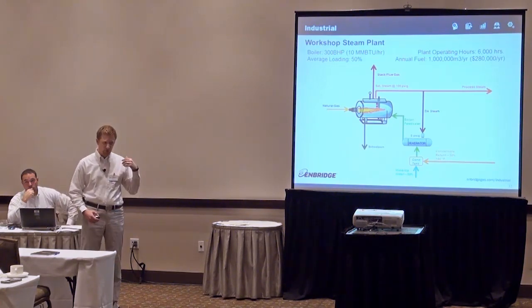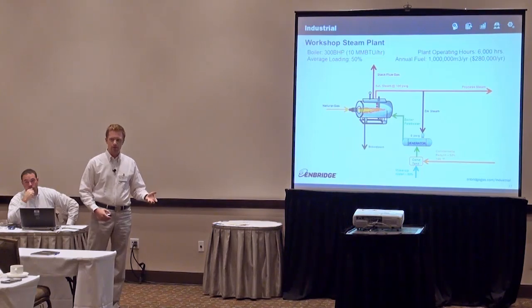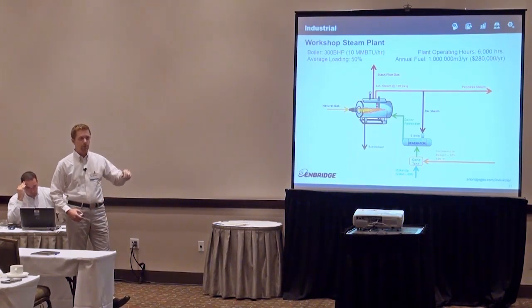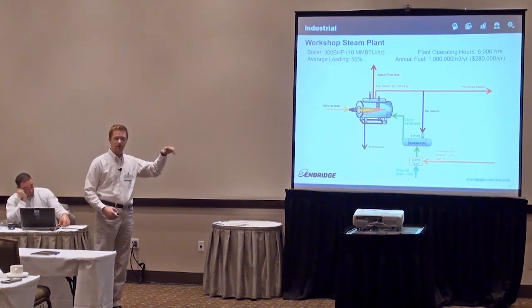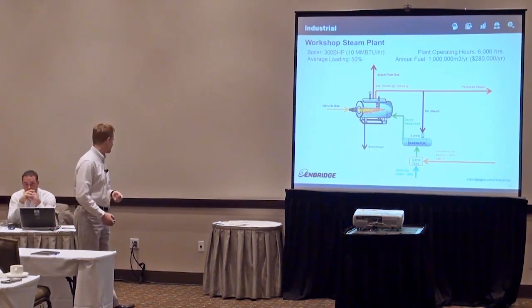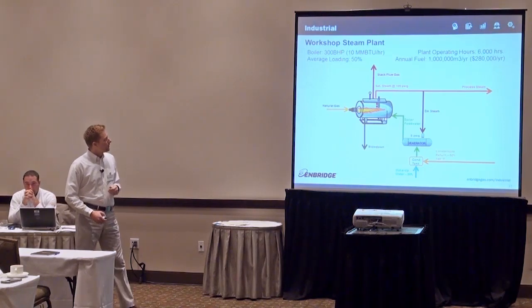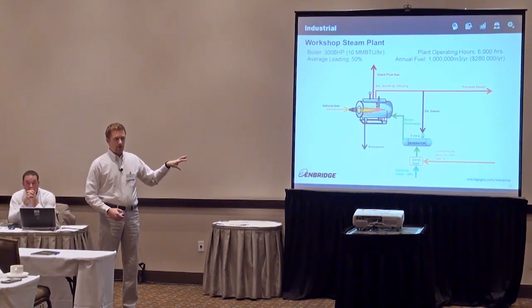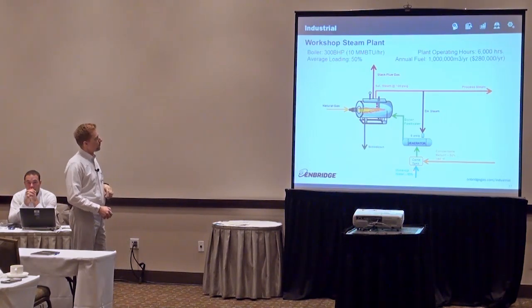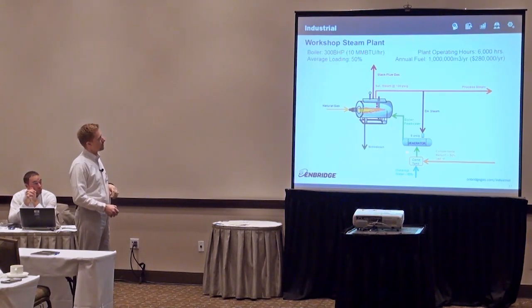Of course, it's purified by the water treatment plant for drinking purposes, but that stuff is still in there. If you're in an area where the water is coming out of the ground, then you're getting all the minerals that are in the groundwater. So, if you're up on the Bruce Peninsula or somewhere up there, I know nobody in here is, but you would be dealing with all sorts of hardness minerals. So we've got to worry about what's going on in there, because that stuff has a significant impact on what's going on in the boiler system. That, of course, comes into your condensate tank, through your deaerator, ultimately into your boiler.